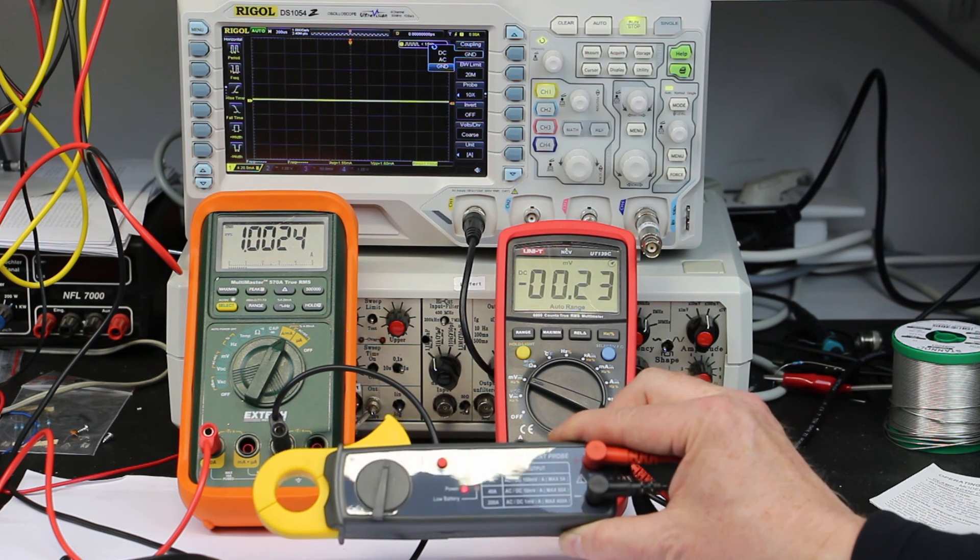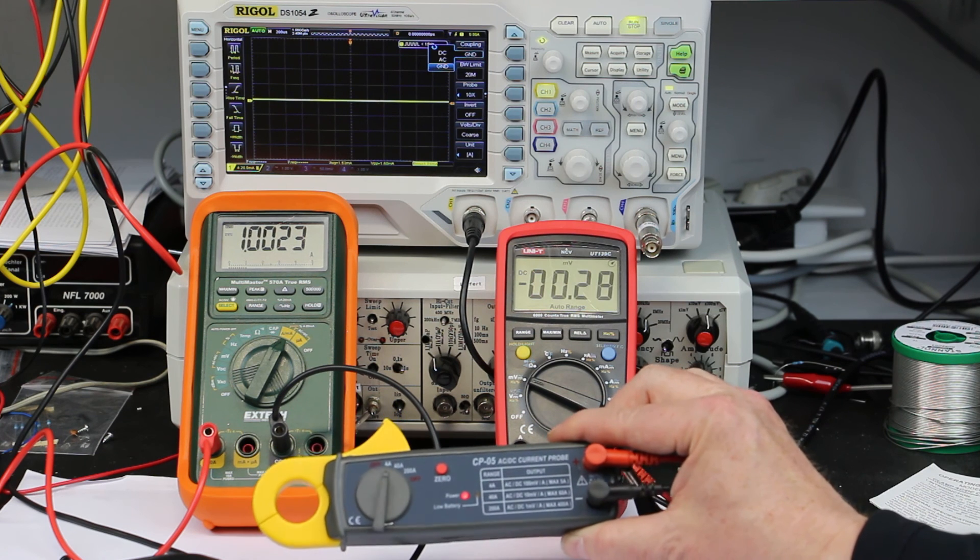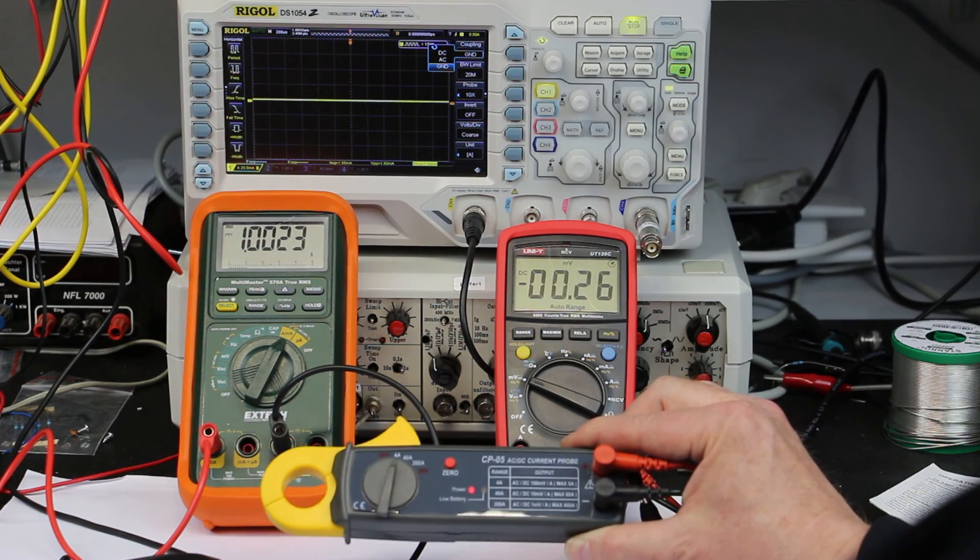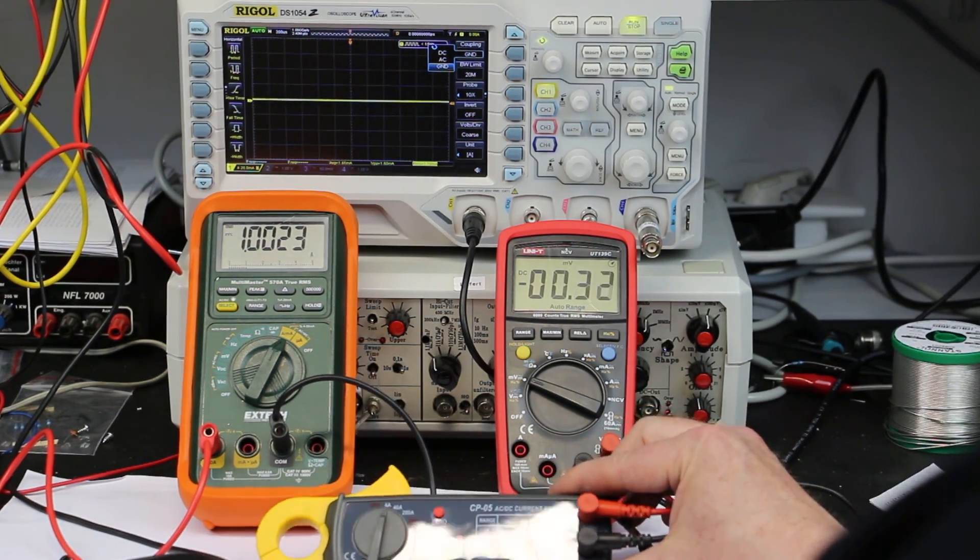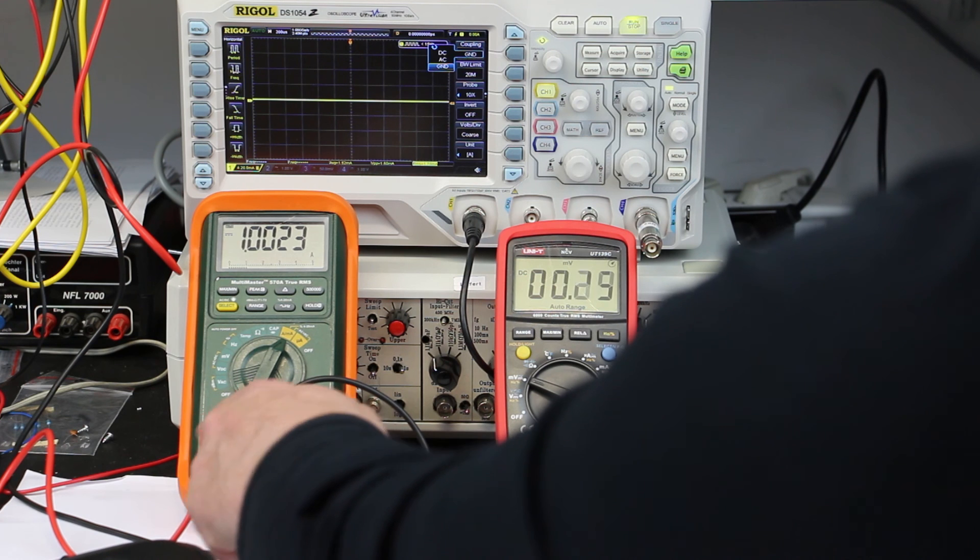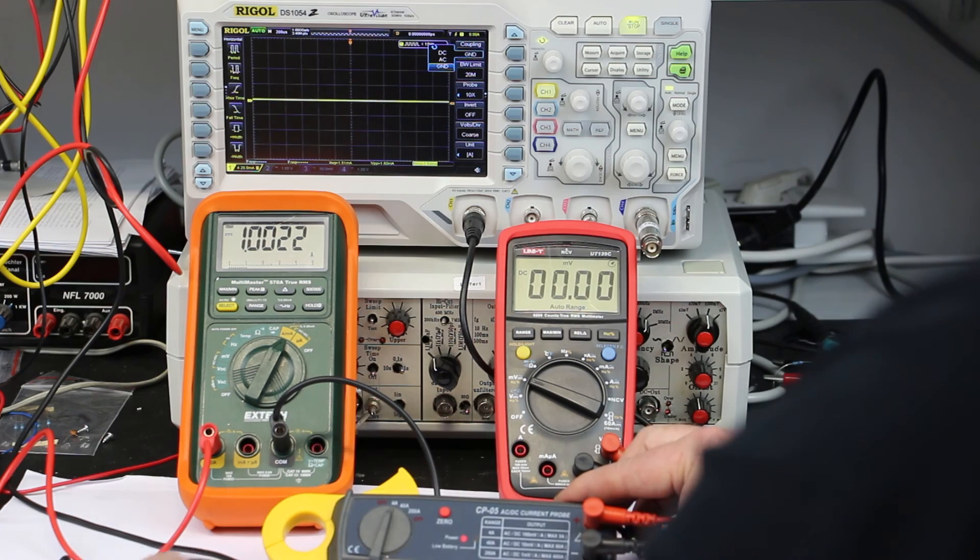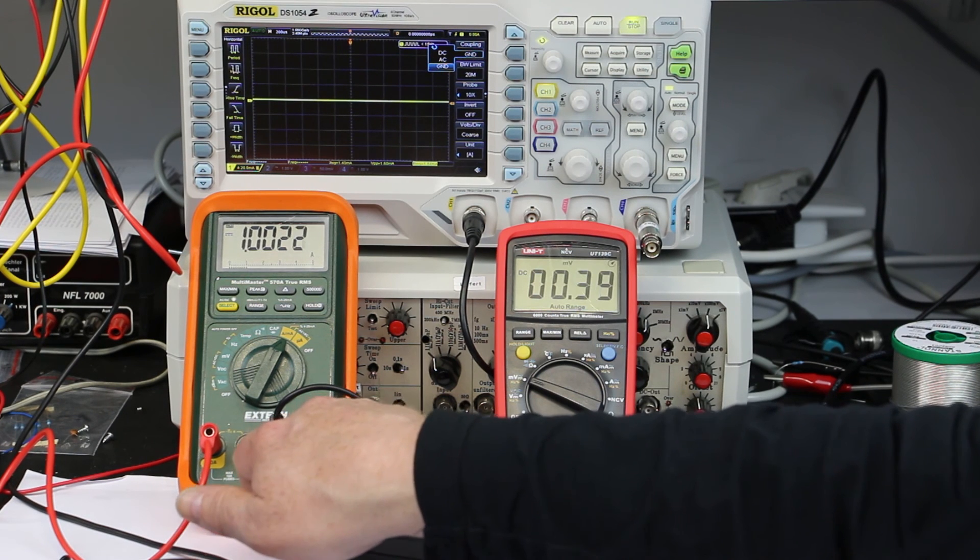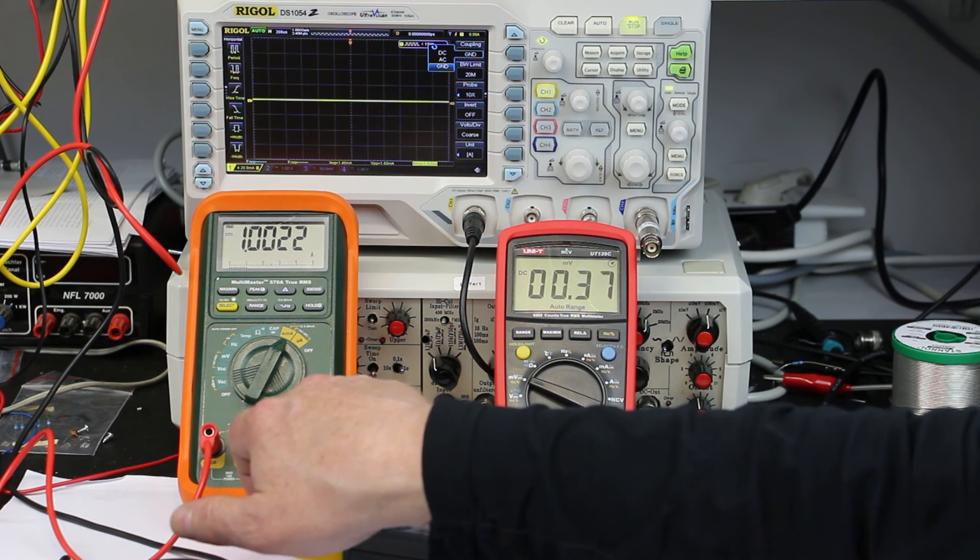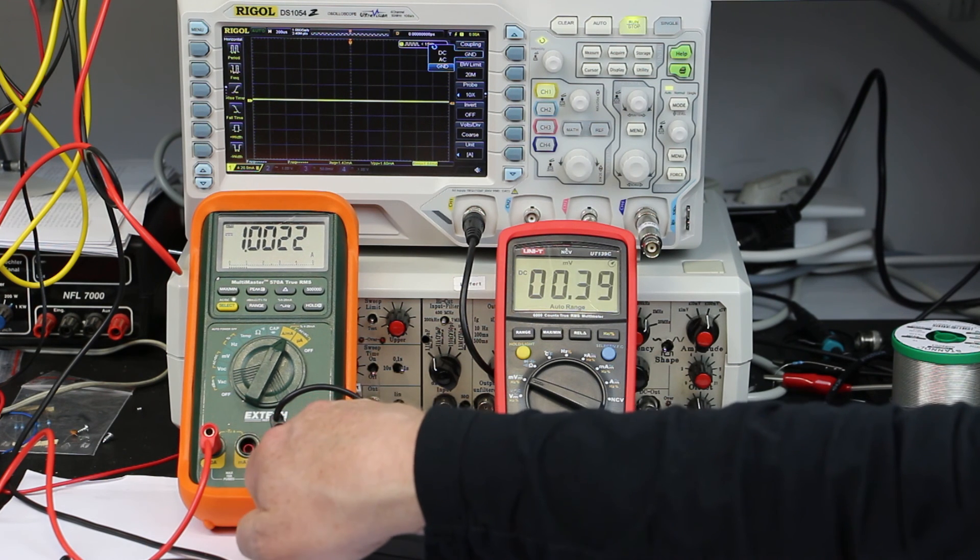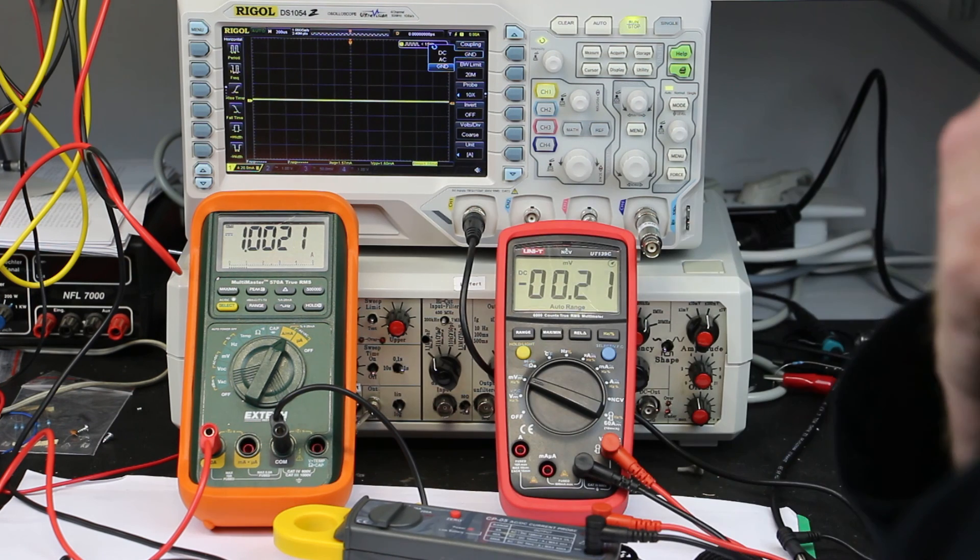I've already made a separate video of how these clamp meter type current probes work. They are totally different to a standard current measurement which you know from your multimeter. This here always works with the same principle. You have a shunt resistor inside, let's say 10 milliohms, and you measure the voltage that is generated by the current flowing through the shunt resistor. And that's the standard way of measuring current.